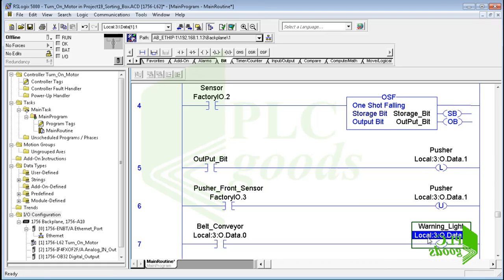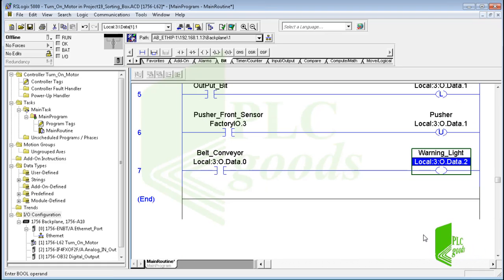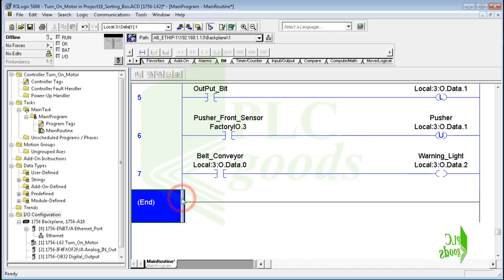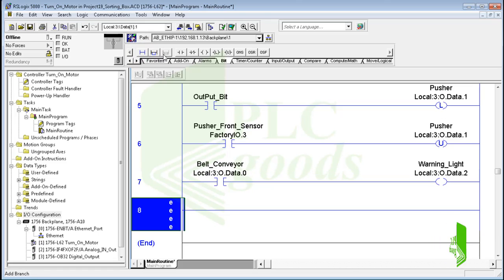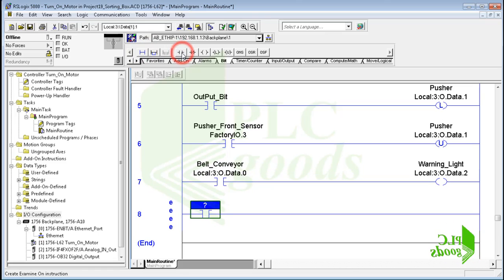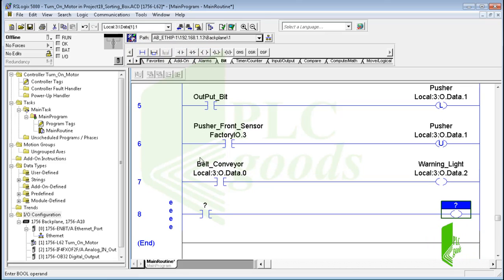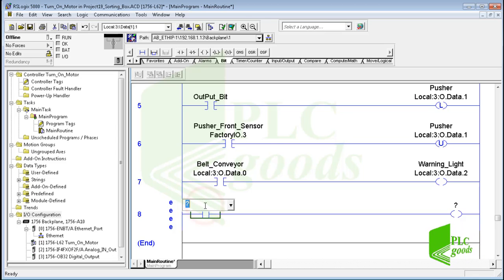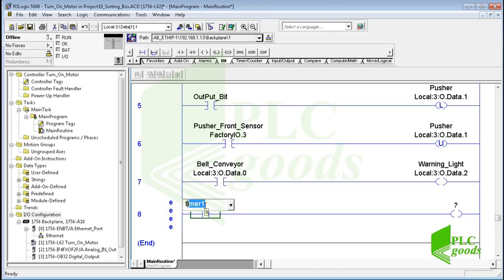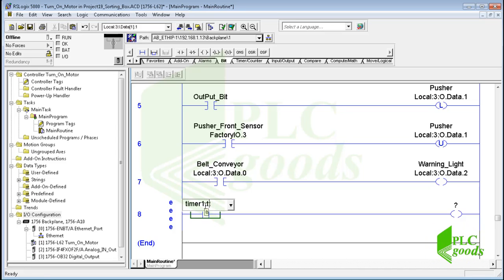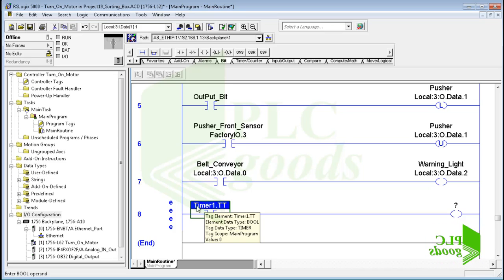Based on the last rung, when the belt conveyor is on, the warning light will be on too. Similarly, let me insert another rung to turn on the warning siren. For this contact, I use the timer timing bit of the first inserted timer, because this bit will be on for 5 seconds before the belt conveyor starts its work.